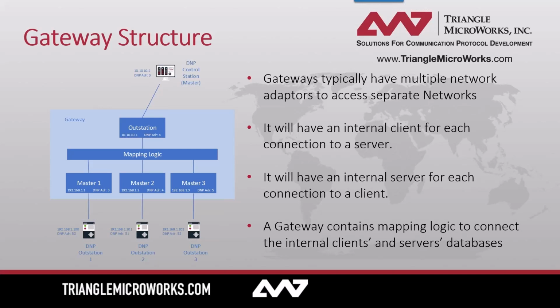So gateways will typically have multiple network adapters and multiple IP addresses. So for example, you'll see Master 1, which hooks up to DNP3, Outstation 1 will be at a different IP address than Master 2 and Master 3. And all of that would be, say, on one logical network. So this would be like 192.168.1. Whereas typically the control station could be isolated to a different network to allow for segregation of different types of data. You'll also want to be able to run all of that through what we call the mapping logic here, which is in the middle. And what that mapping logic does is it allows you to pick and choose the important bits of information, maybe your class data, your report data, anything like that, can be all mapped up to the outstation, which is what is presented upward.